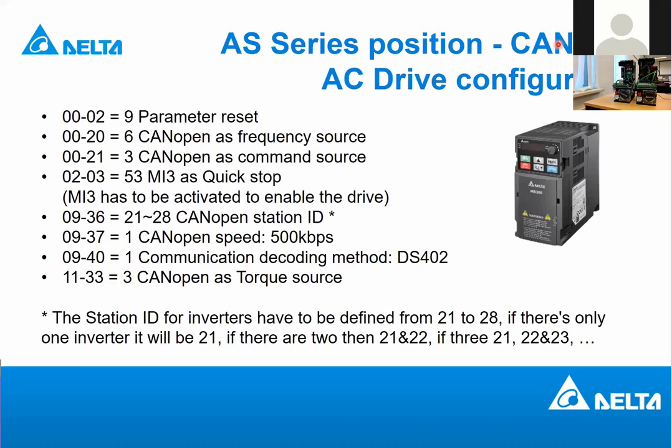The next step now, we're going to set the communication protocol. So let us set CANopen as frequency source, also set CANopen as command source. We'll do that with parameters 0020 and 0021. So let's set 0020 to 6, and we set 0021 to 3. So let's go.